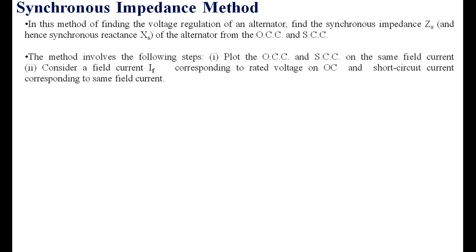The method involves the following steps. The first step is to plot the open circuit characteristics and the short circuit characteristics on the same field current base. You have to take field current as a common base, then take the open circuit voltage on the Y-axis as well as the short circuit current. You have to take per-phase values, because usually in numerical problems the line-to-line voltage is mentioned, which you must convert into phase voltage before drawing the open circuit characteristics.